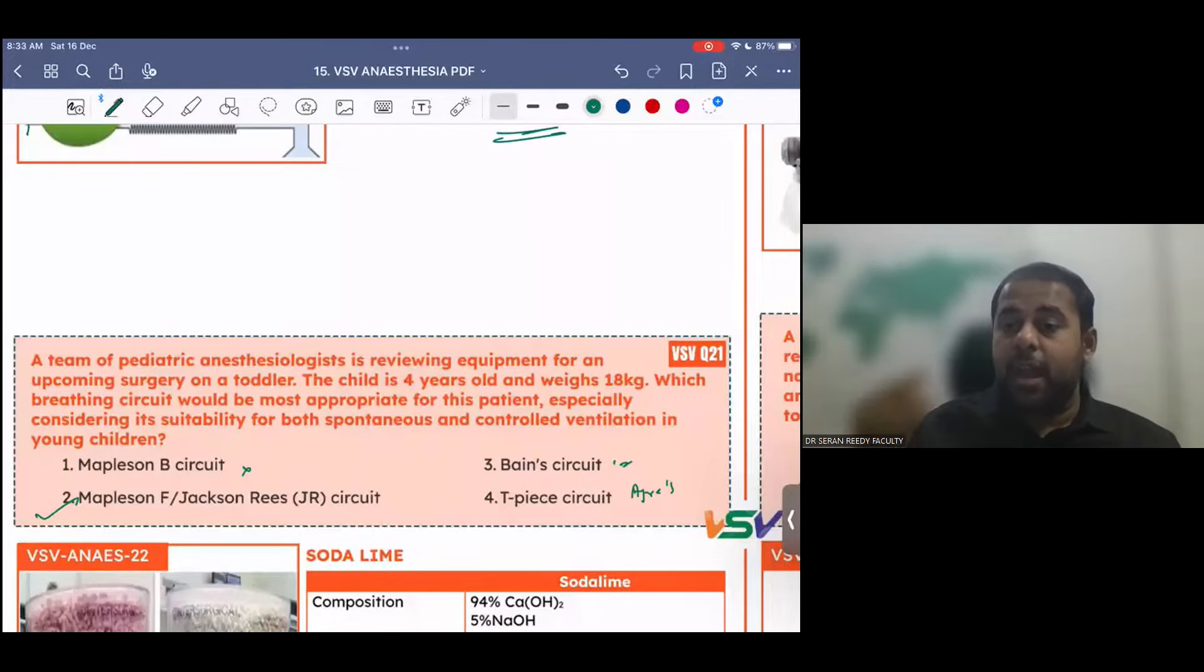Among ABCD, EF, ABCD are used in adults. EF are used in children. And among the ones which are popular, A and D in Mapleson A, and Mapleson D in adults, and Mapleson F in children. Mapleson A, best circuit for spontaneous ventilation in adults. Mapleson D, best circuit for controlled ventilation in adults. Mapleson F or Jackson Rees circuit, the best circuit for both spontaneous and controlled ventilation in children.